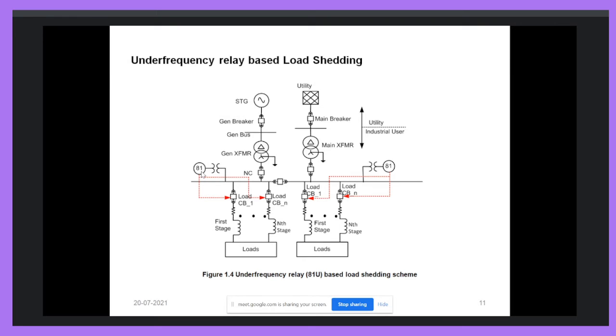The settings of these frequency relays are determined for the worst operating scenario, because we do not want our system to become unstable. So we perform the system analysis and determine the setting of the frequency relay and the amount of load which should be disconnected for the worst operating scenario. So in this case also, more load will be disconnected. Why? Because we made the settings for the worst operating scenario, meaning the maximum load generation imbalance.